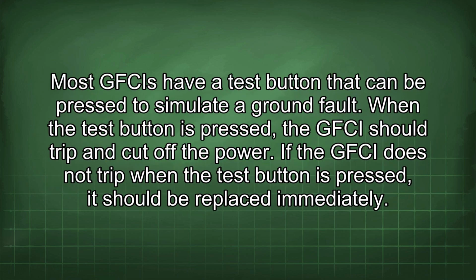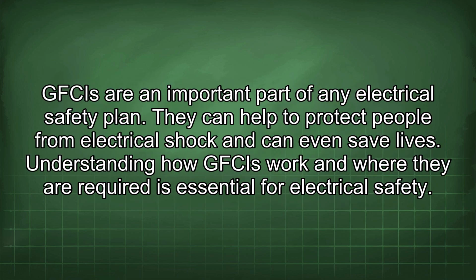Most GFCIs have a test button that can be pressed to simulate a ground fault. When the test button is pressed, the GFCI should trip and cut off the power. If the GFCI does not trip when the test button is pressed, it should be replaced immediately. GFCIs are an important part of any electrical safety plan. They can help to protect people from electrical shock and can even save lives. Understanding how GFCIs work and where they are required is essential for electrical safety.